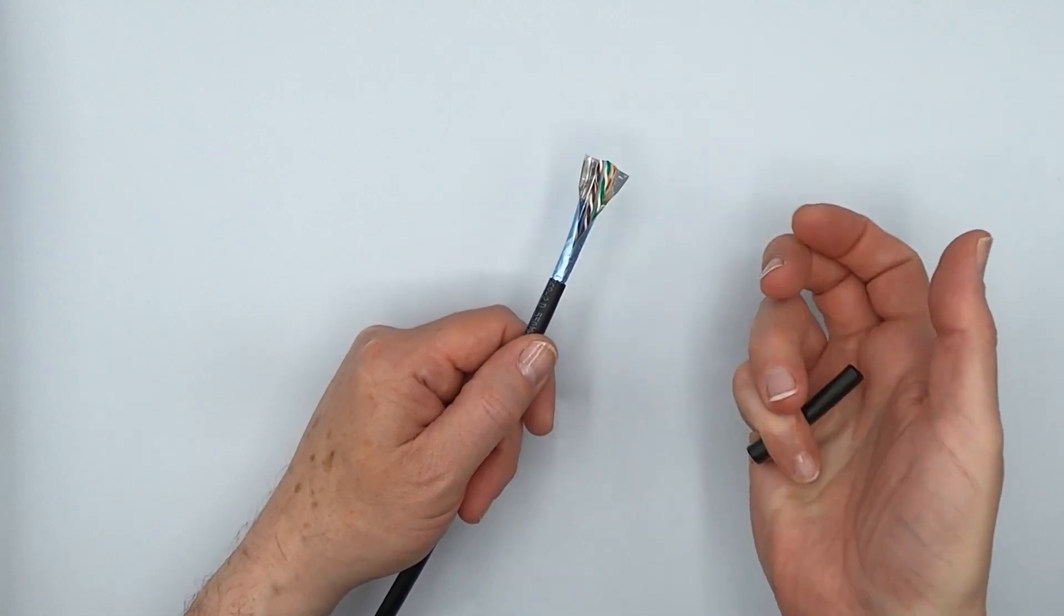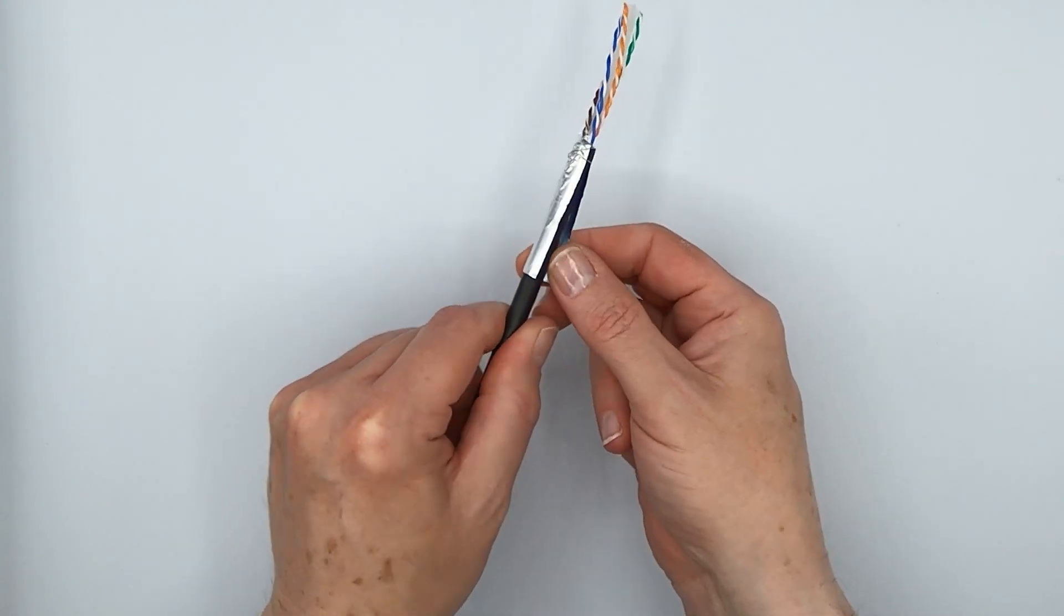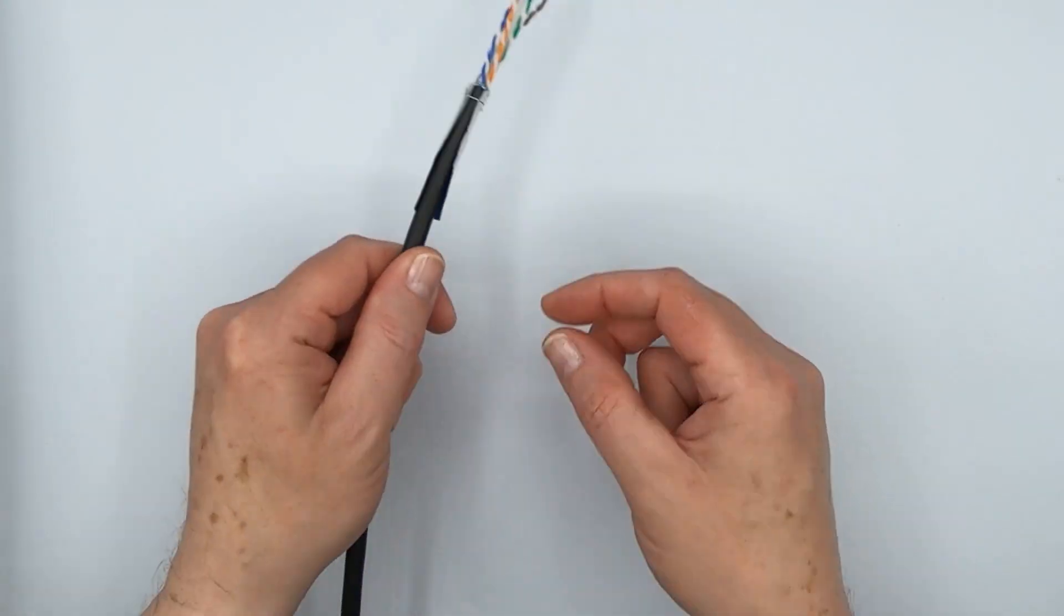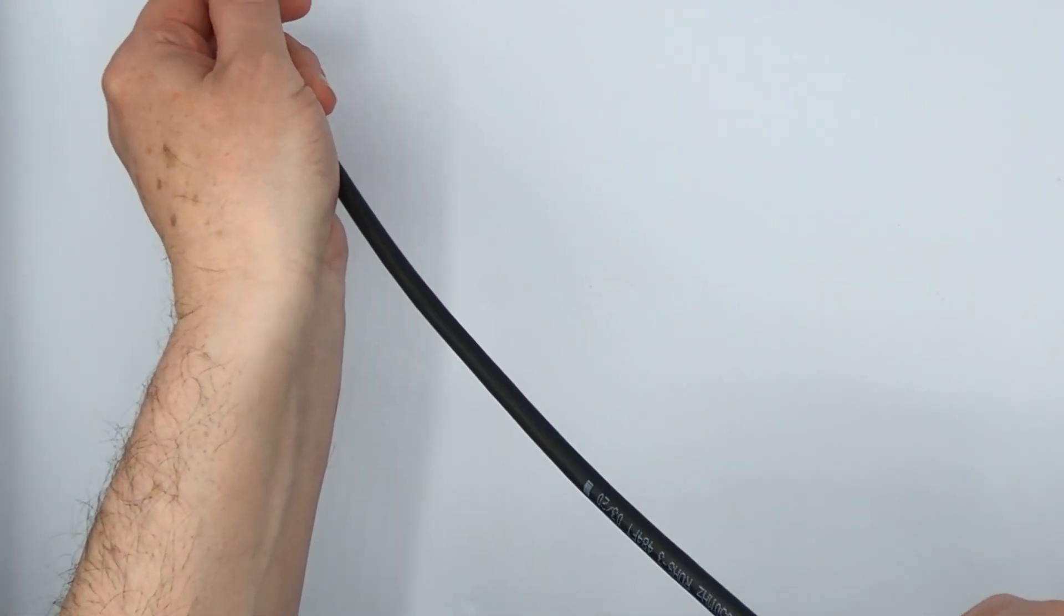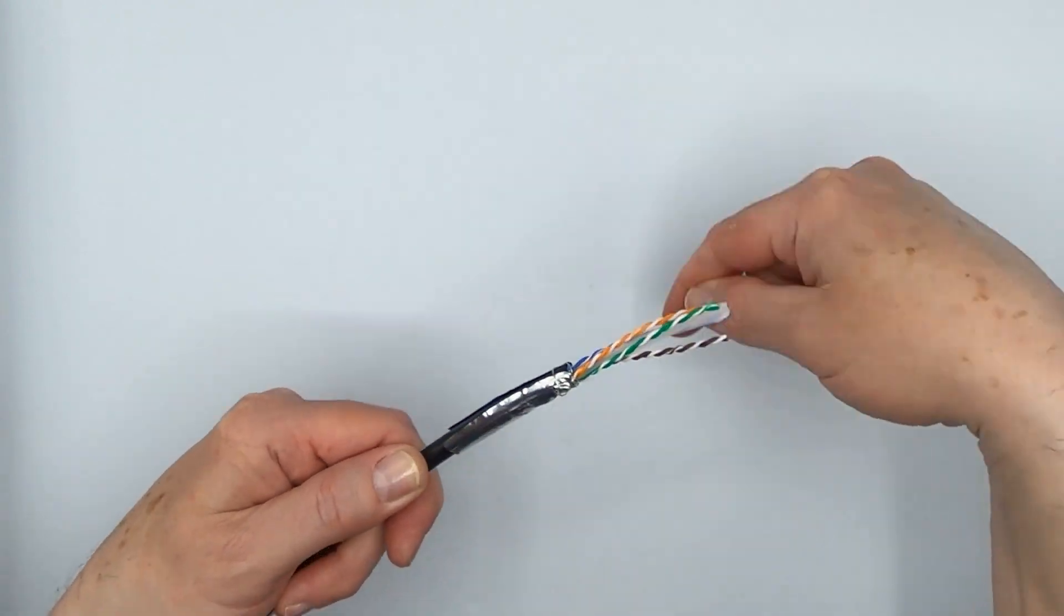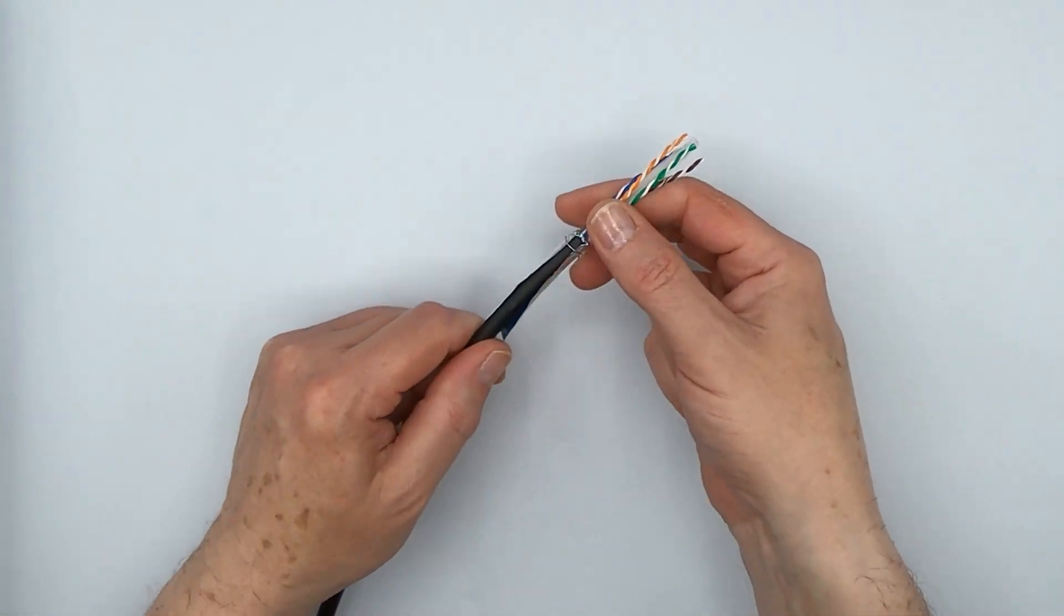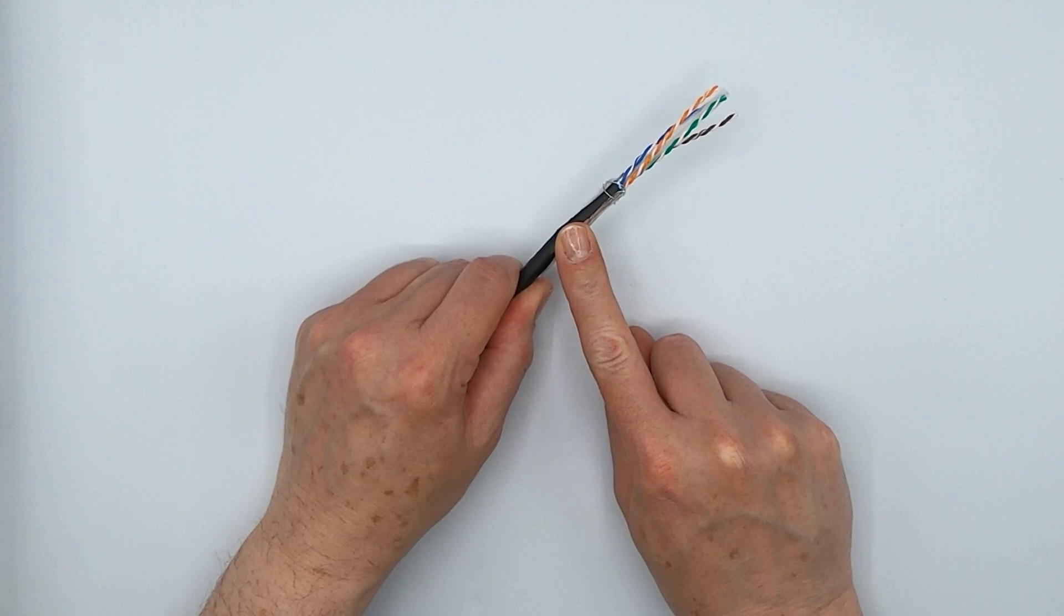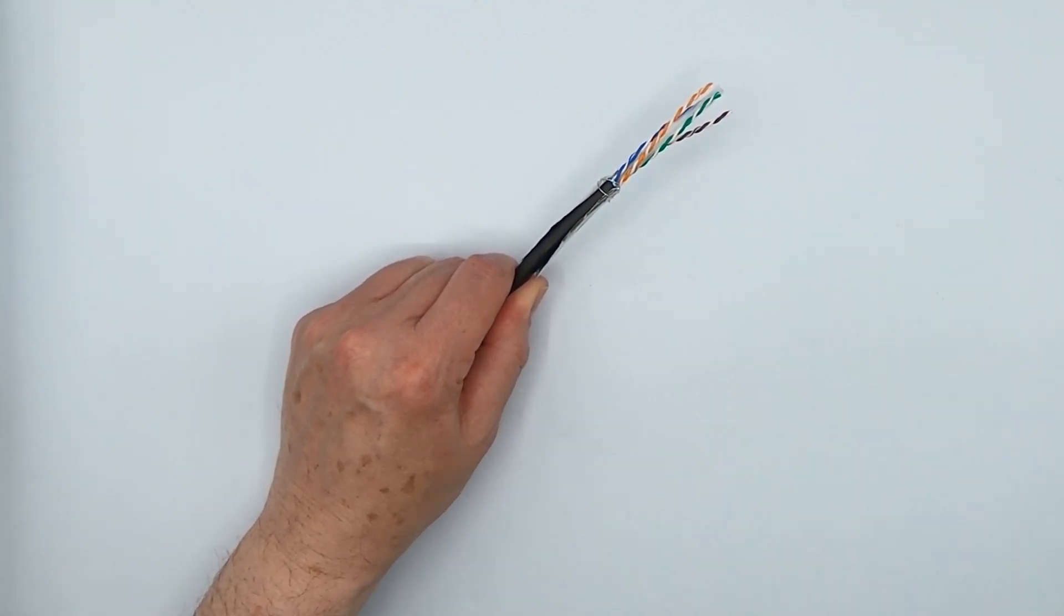Well, the traditional way of dealing with that has been to fold the cable shield backwards, like so, right along the cable jacket, take the drain wire that's in here, and then fold it and then wrap it around. That's been the traditional way of dealing with it. And it works. There's nothing wrong with doing it that way.